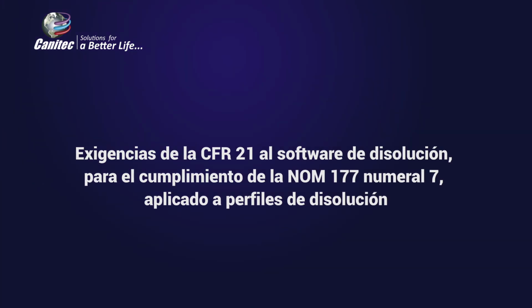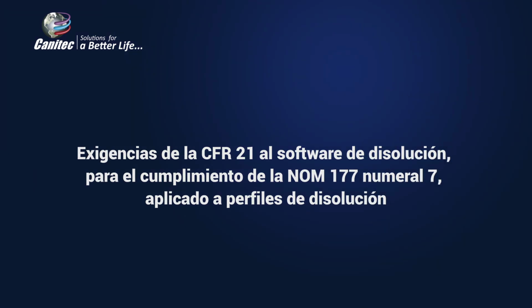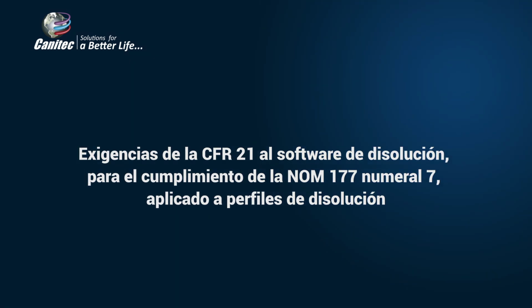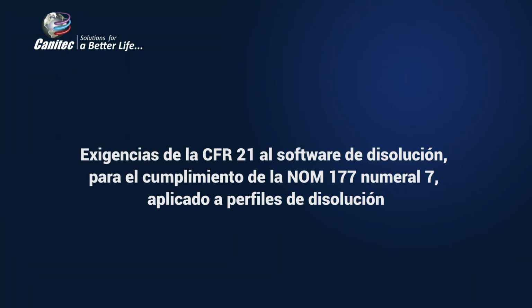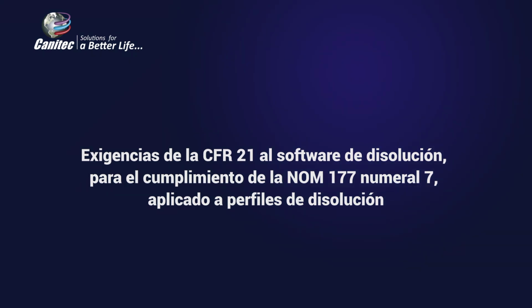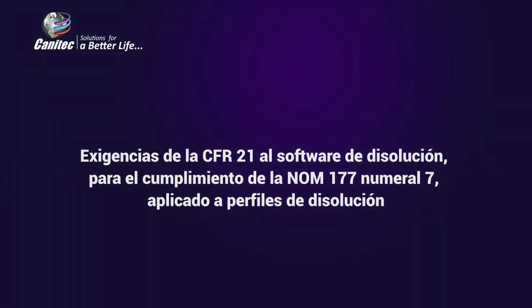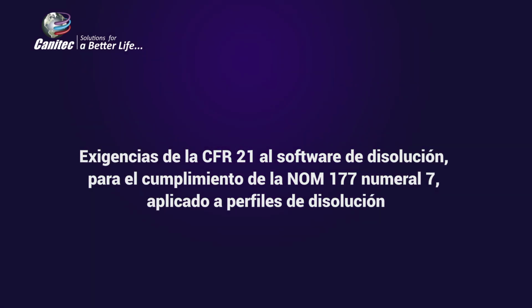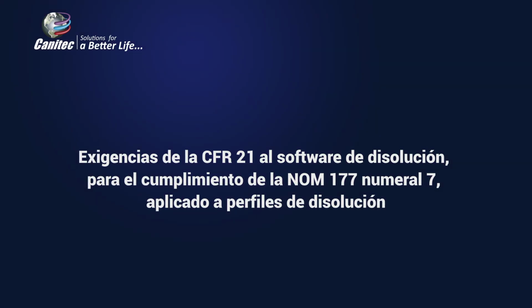I load my software and I press run. I give it a batch ID. You must give it a batch, otherwise it will not proceed. And the software will proceed to ask me to put my tubing into my blank vessel. Because I've connected the vessel to a pump, it will pump the solution into the cell. However, if you don't connect the tubing to the pump, but directly to the spectrophotometer, you can place the sample in a cell manually.